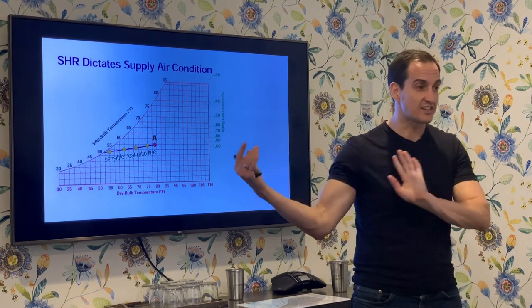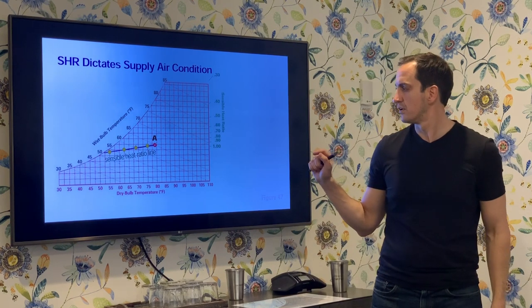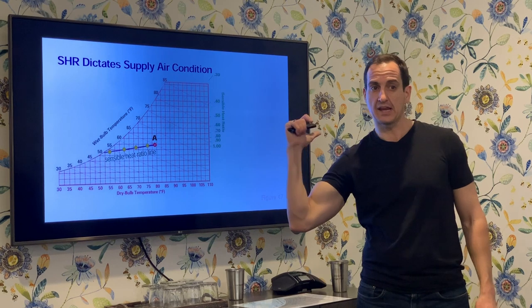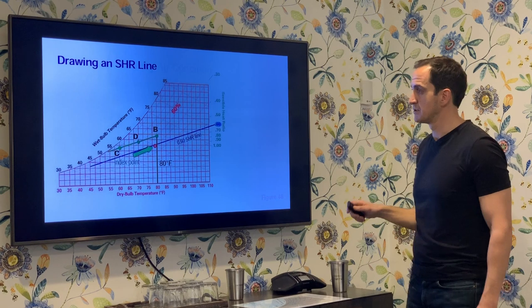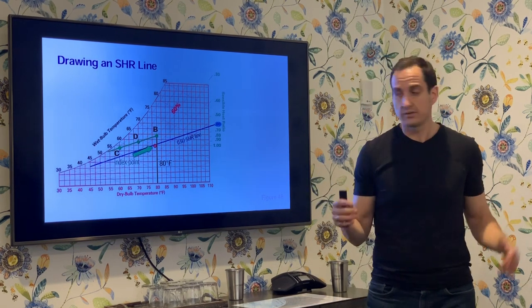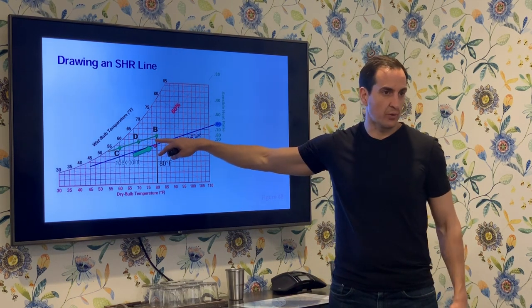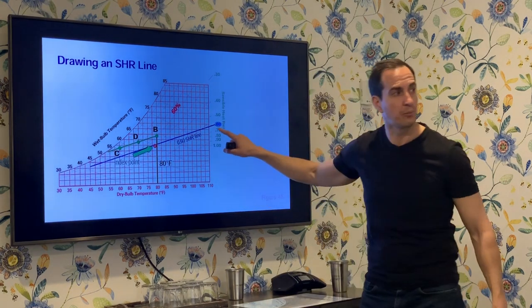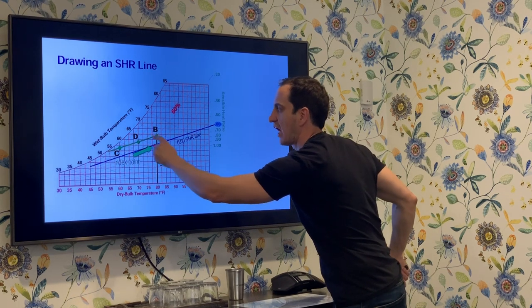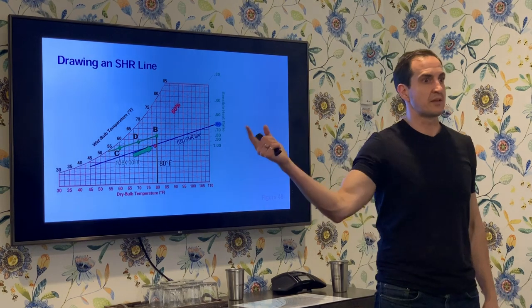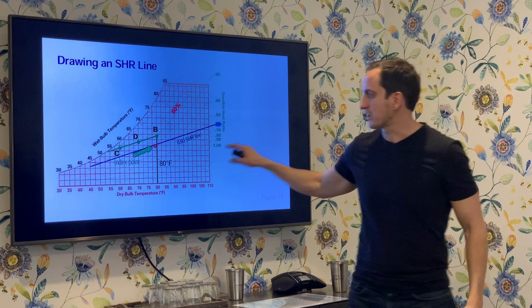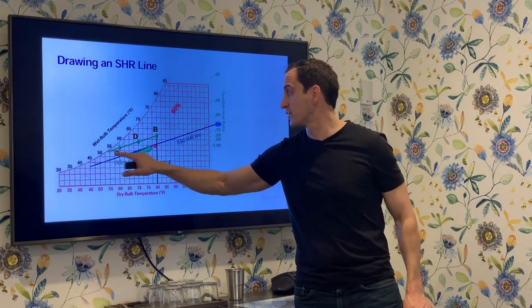We're talking about how we process air: how we change temperatures, cooling, heating, humidification, and dehumidification. If I was at any other starting point and knew my sensible-latent balance, I could take my sensible heat ratio line — say 0.6 — translate it to my new starting point, and know that I need to deliver air somewhere along that line to counteract the energy balance in my room. In a well-engineered room where I know exactly what the lights are doing and where the moisture is coming from, I can use this line to determine whether I need to deliver a little air at a very conditioned state or a lot of air at a slightly conditioned state.